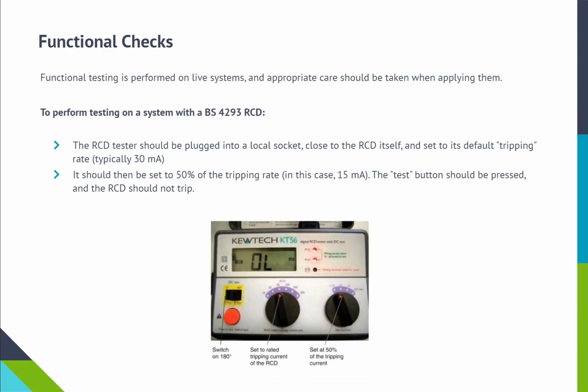To perform testing on a system with a BS 4293 RCD, the RCD tester should be plugged into a local socket close to the RCD itself and set to its default tripping rate, typically 30 mA. It should then be set to 50% of the tripping rate, in this case, 15 mA. The test button should be pressed, and the RCD should not trip.